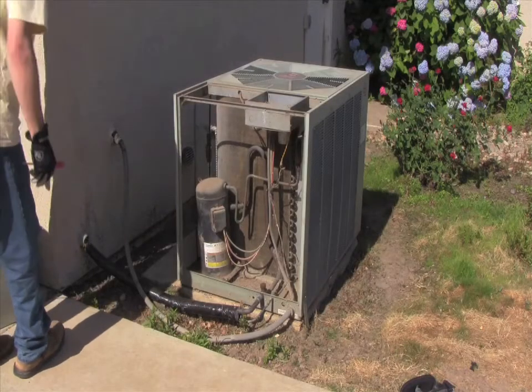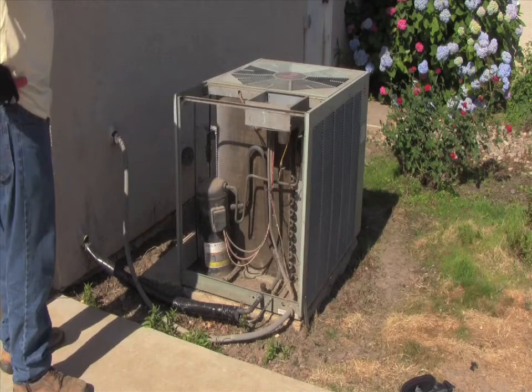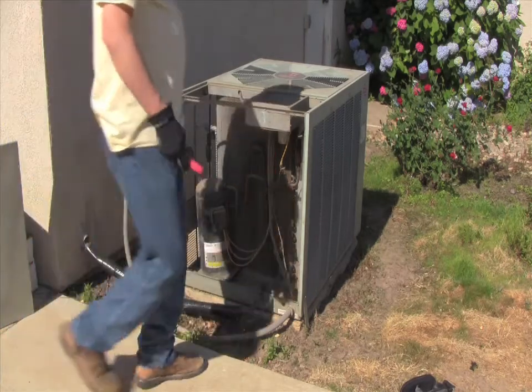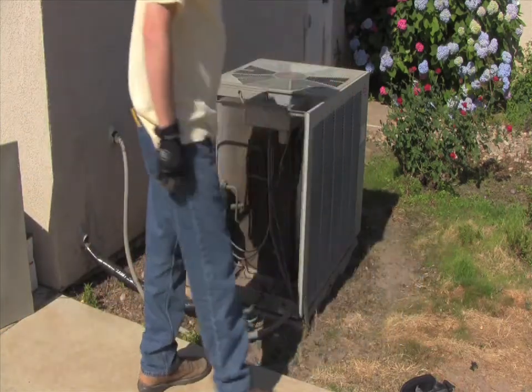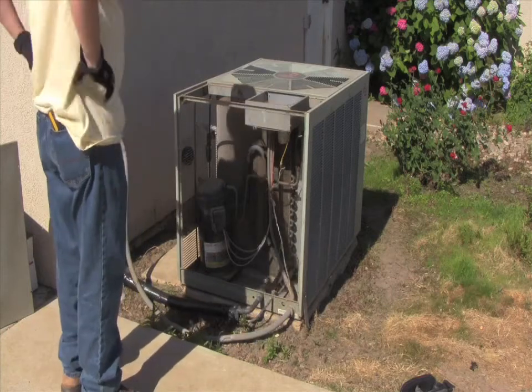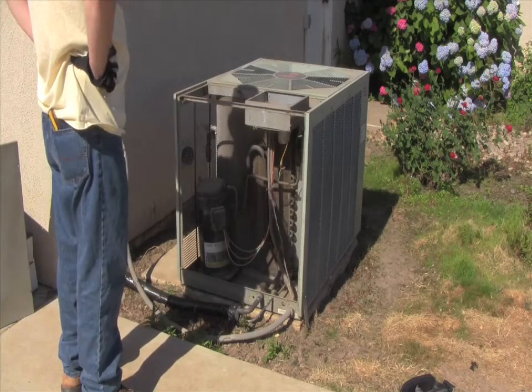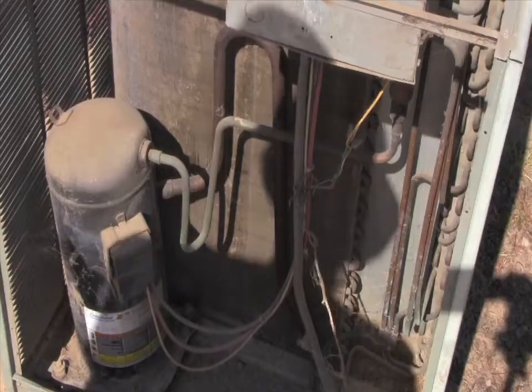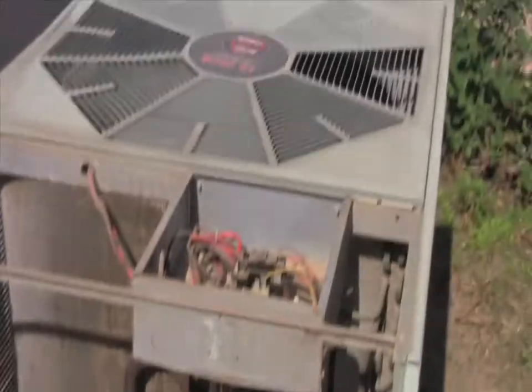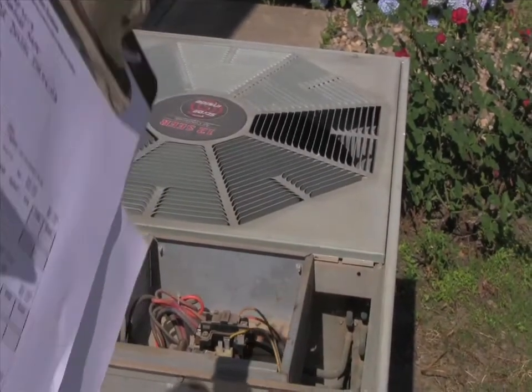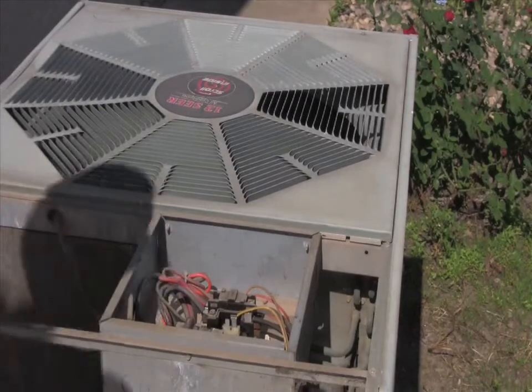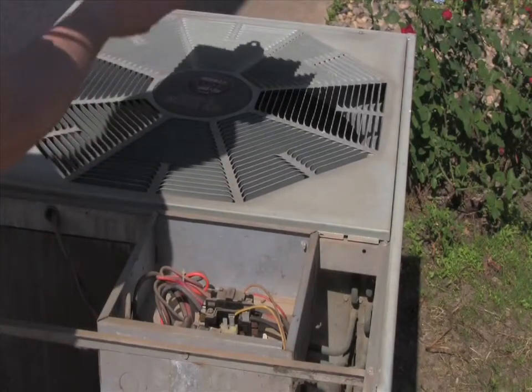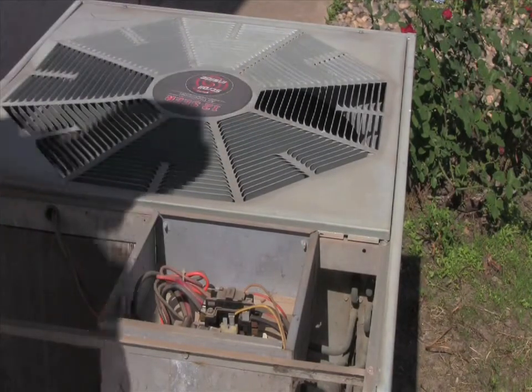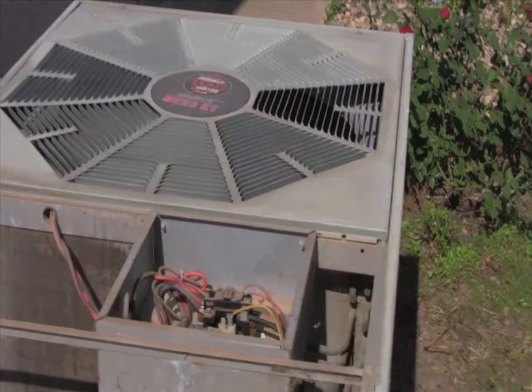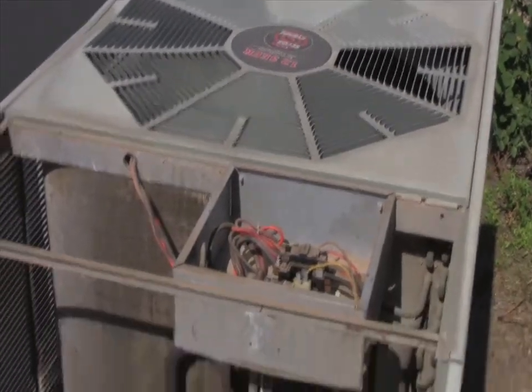At this time, we're going to ask the customer to turn on their air conditioning system, full blast, drop it down to like 66 degrees or whatever it is so that it runs continuously. One other item, do not put anything on that right there, because when you do, it's going to blow it away when you switch it on. So you don't ever want to place anything on the fan.